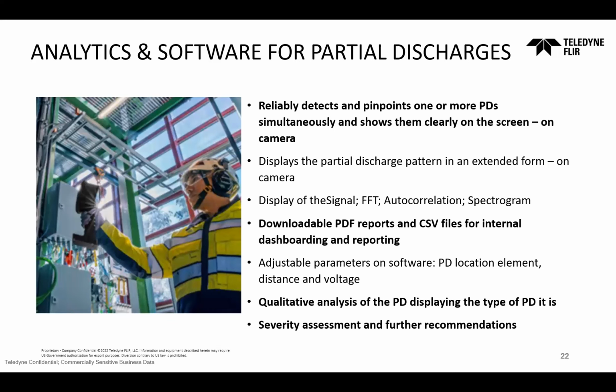As I said, downloadable PDF reporting and CSV files, adjustable parameters and software, PD location element, distance, and voltage. Voltage and location element are fundamental for the qualitative analysis and the severity assessment. So it's not the same to have a partial discharge in a bushing than in an isolator, than in a transmission cable or in a cable termination.